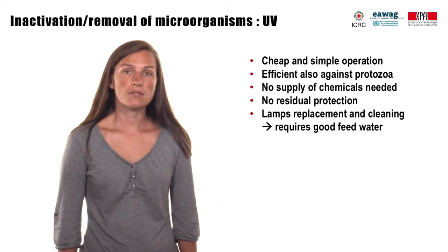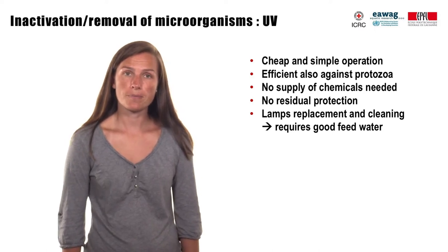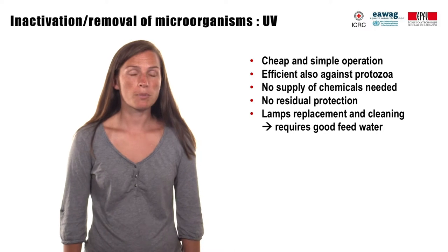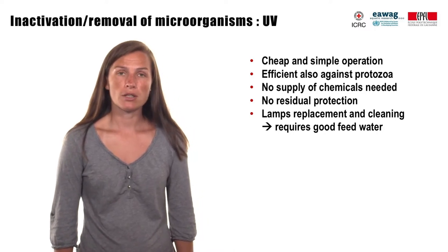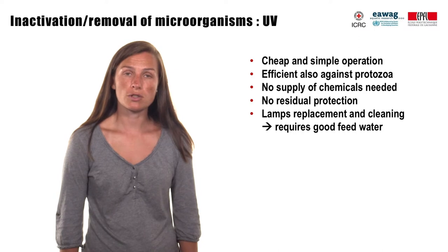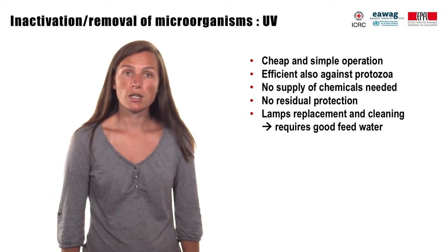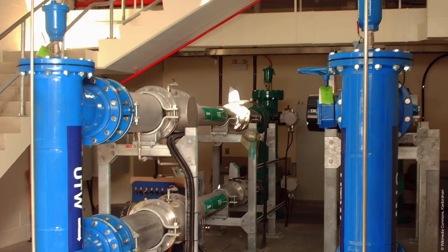In contrast, disinfection with ultraviolet light (UV disinfection) is cheap and relatively simple. It inactivates microorganisms by damaging their DNA and RNA. In contrast to chlorination, it is also efficient against protozoa. No supply of chemicals is also an advantage of this method. However, it does not provide residual protection, requires reliable power supply and frequent cleaning of the UV lamps, which are the source of UV light. As with chlorination, it is sensitive to turbidity and water should be clarified before UV treatment.